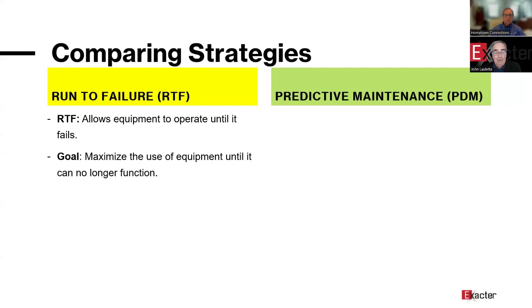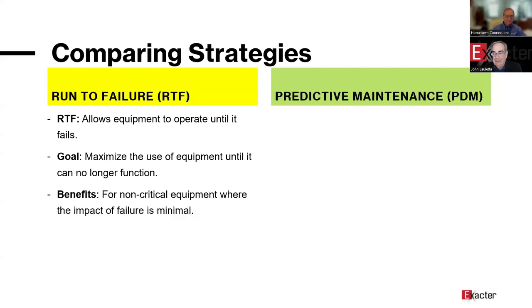Now, the goal of that, of course, is to maximize the use of the equipment until it actually does fail. So a lot of utilities will use this as the reason for run to failure. Let's get every inch and minute out of that equipment before we replace it. For non-critical equipment, that's okay. But really, is there a piece of equipment on the distribution grid that's non-critical? Because is there a piece of equipment that if it fails, you won't have an outage? Or if it fails, something worse could happen, like a lightning arrestor? If a lightning arrestor fails, the equipment it's protecting may get damaged at the next lightning strike in the area.